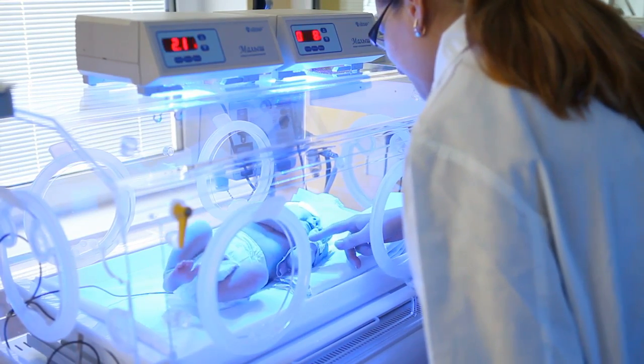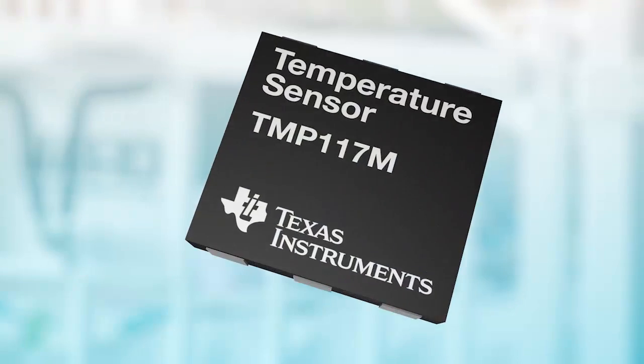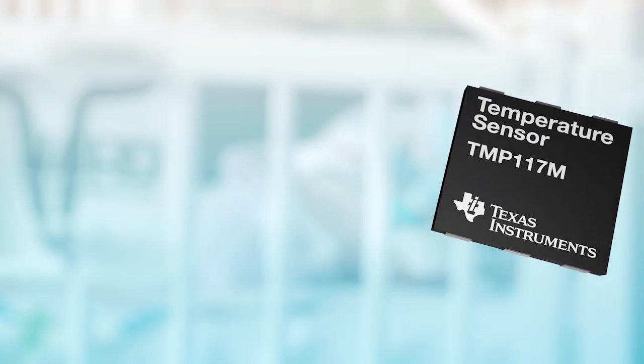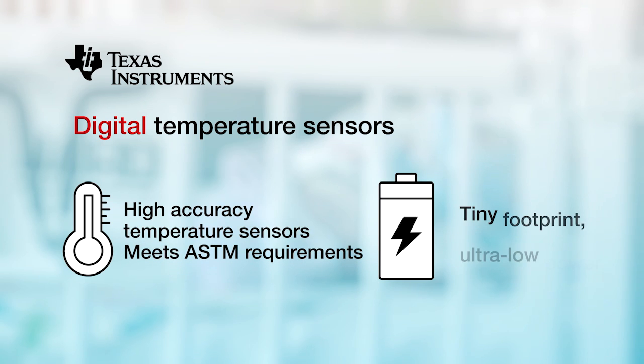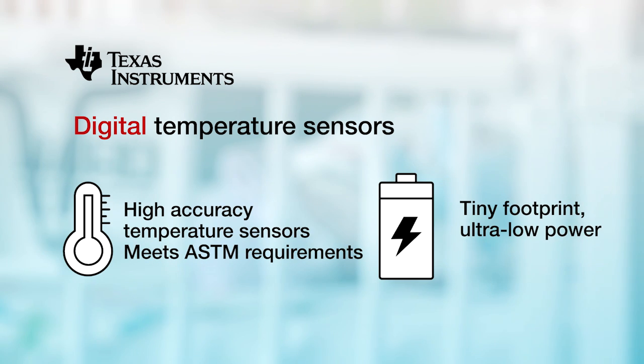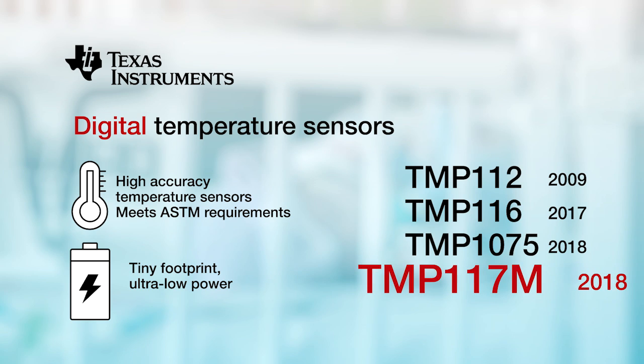Our intention was for this technology to be inside of an ICU, therefore you cannot sacrifice the accuracy of the system. So we began to look at what companies have very small thin chips that nonetheless have quite a bit of accuracy. We learned about this suite of chips that Texas Instruments was beginning to introduce, and step by step the accuracy was approaching clinical grade accuracy — and indeed the most recent chip that is newly announced meets that constraint.